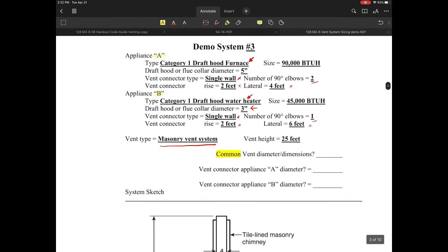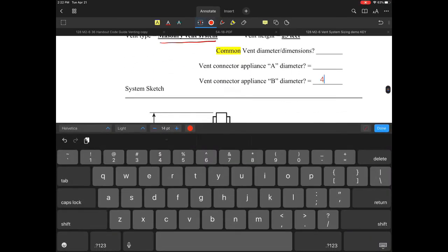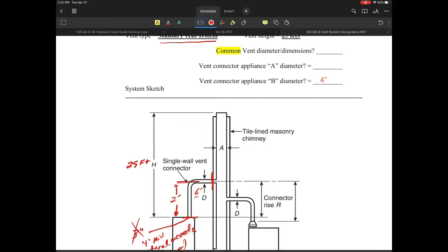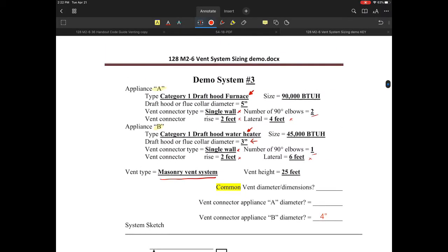A 25-foot high vent system with a two-foot rise would simply be 56,000 BTUs — exactly smack dab in the middle. It's a straight proportional linear ratio. We have a 45,000 BTU unit, and the capacity is good for 56,000 BTUs for the vent connector. We are well within our guidelines. So appliance B is going to be a four-inch single wall connector.